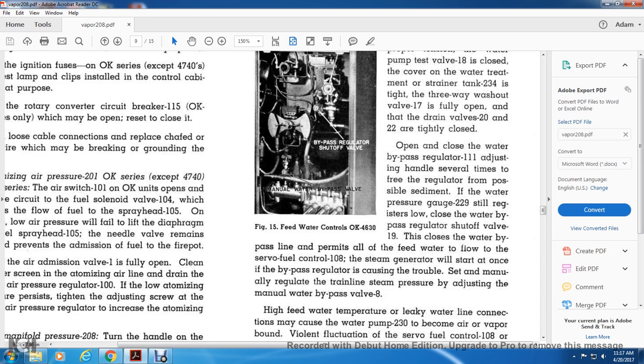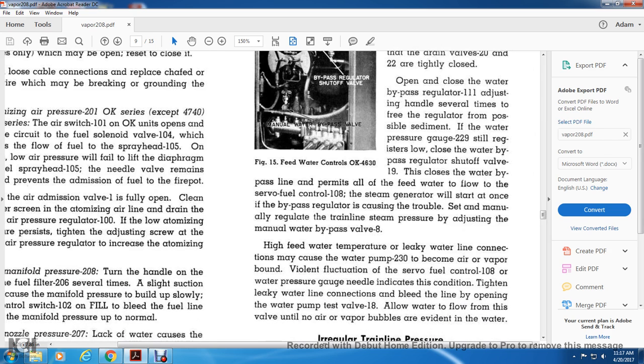If the regulator is low, close the water bypass regulator. Shut off valve 19. The closed water bypass line permits all the feed water to flow to the servo fuel control 108. The steam generator will start at once if the bypass regulator is causing the trouble. Manually regulate the steam pressure by adjusting the manual water bypass valve 8.